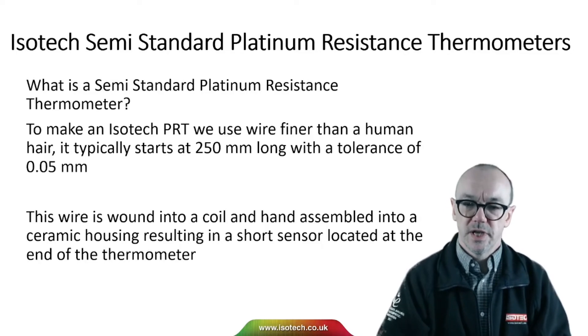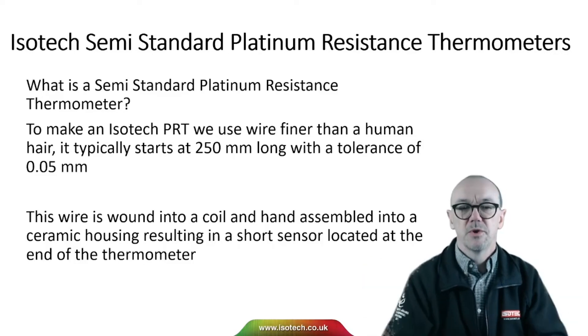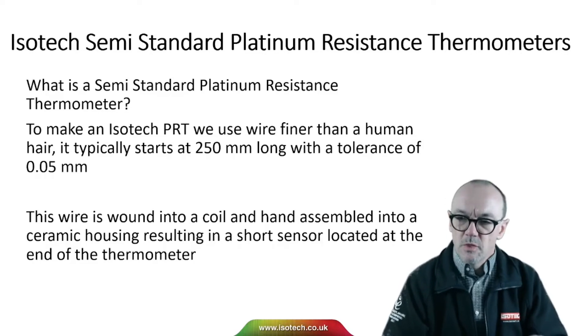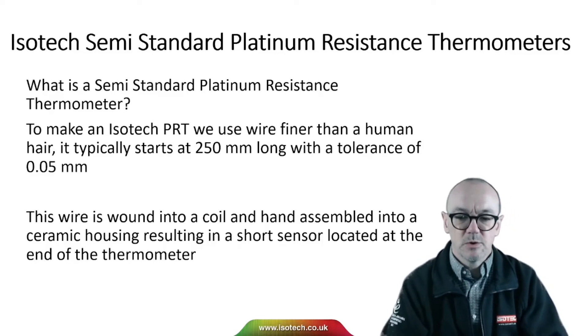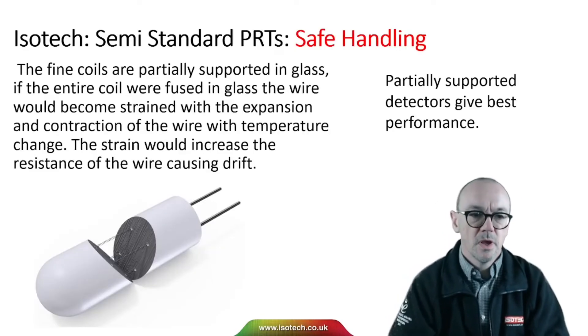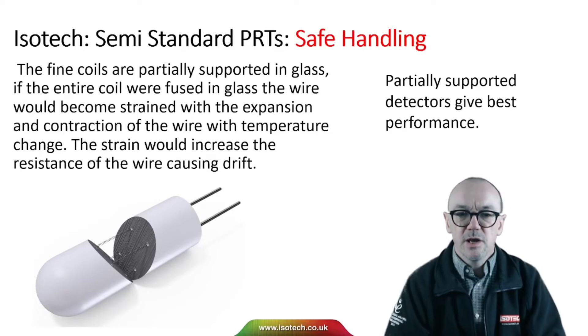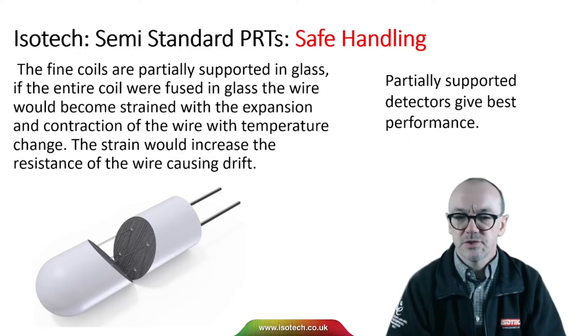To make an Isotech PRT, we start with wire so fine you can barely see it — finer than a human hair, typically 250 millimetres long with a tolerance of just 0.05 millimetres. That wire is wound into a coil and hand assembled into ceramic housing elements to create the sensor. Those fine coils are partially supported in glass. If the entire coil were fused in glass, the wire would become strained with the expansion and contraction of temperature change, and that strain would increase the resistance of the wire causing drift.